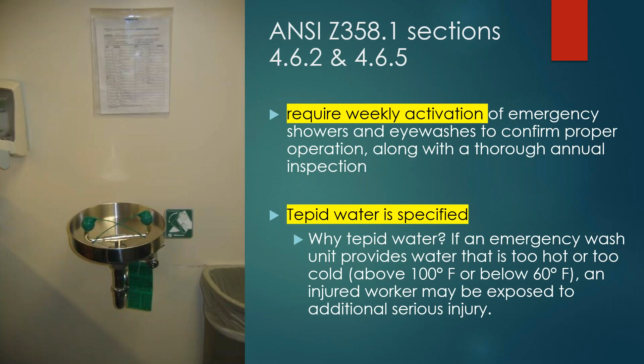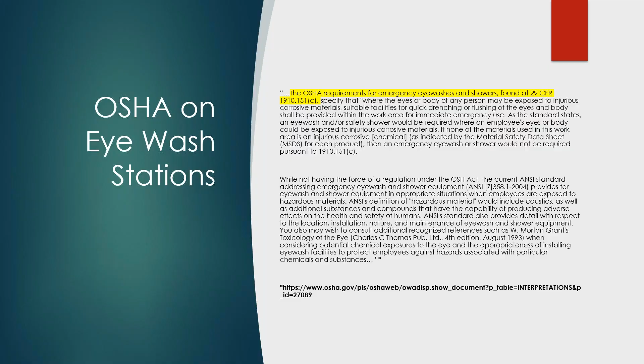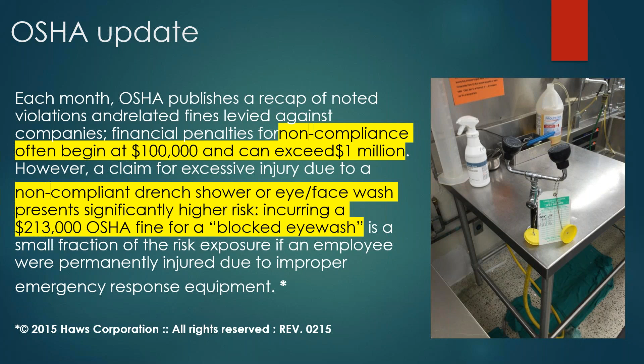OSHA is the big one because of this. OSHA requirements for emergency eye wash stations are found in 29 CFR. The reason this is such a big deal is because OSHA, unlike other entities we talk about like AAMI, can actually levy fines. There are legal implications with OSHA, and you can see $100,000 and can exceed $1 million fine should there be a problem.